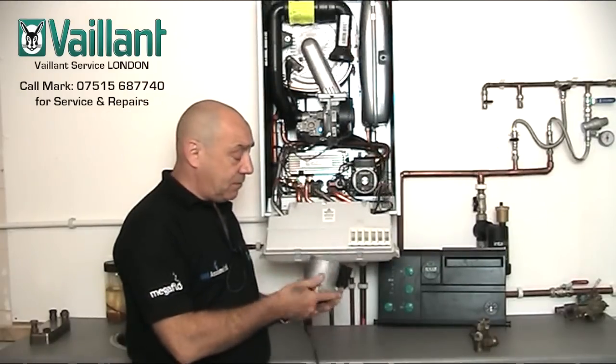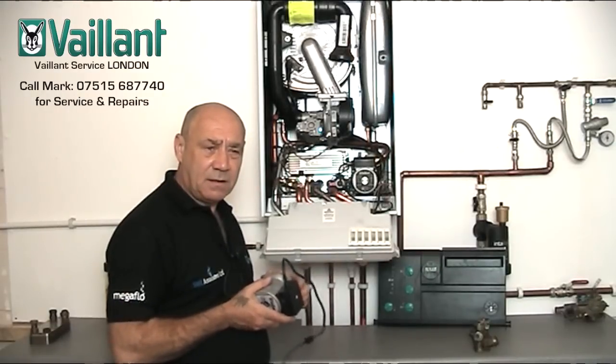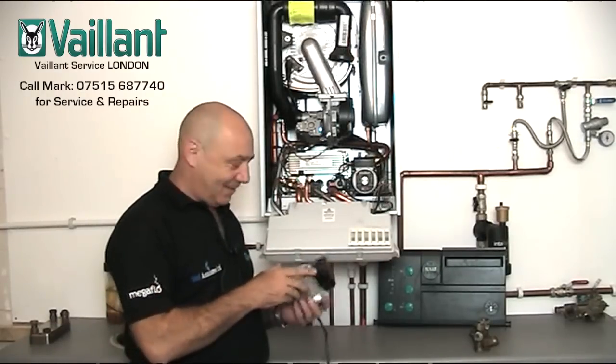So, Vaillant Ecotec pumps — grey face, black face. This one's likely to fail, especially if it's making that sort of noise. There you go.